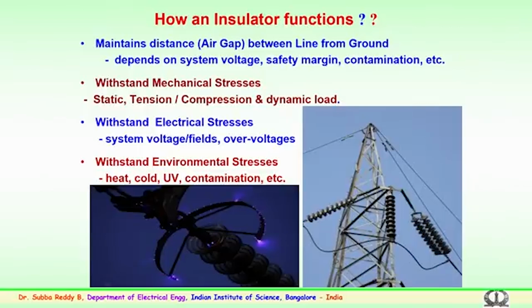So, the insulator has to withstand mechanical stresses. Mechanical stresses may be static in nature, such as tension or compression, or due to dynamic loading because of wind or any natural calamities which may happen. So, they have to withstand the dynamic and compression loads. Apart from these mechanical stresses, insulators have to withstand electrical stresses as mentioned: the system voltages, which are the normal working voltages and fields, and over voltages. As I mentioned, over voltages comprise lightning over voltages, switching over voltages, or sometimes, for a short duration, power frequency over voltages.